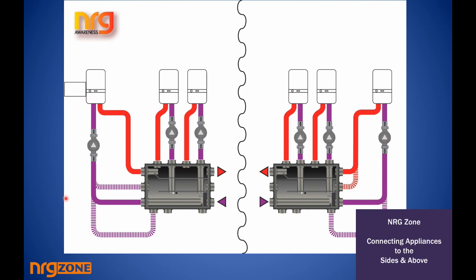Now if we want to turn the unit upside down, we want to face it upwards. So remember what I told you, you would now have to use what would have been originally described as the flow chamber, but it's now the bottom chamber. You collect your return water here, and that's taken back to the respective boilers, and then the heat from the boilers is delivered into the top chamber.